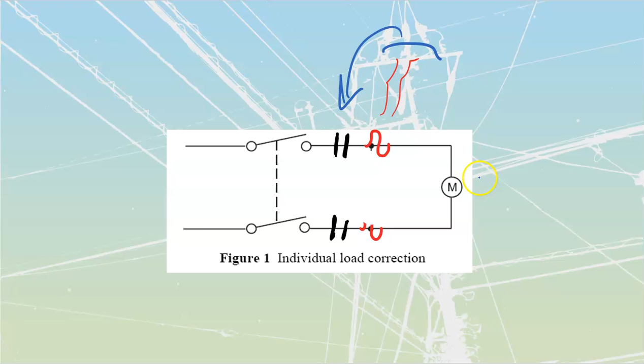What's it doing? Well, it's monitoring the current. Too much current goes through, creates too much heat, trips the switch, shuts the motor itself off. It just prevents us from burning out motors. This is sized based upon my motor's amps. There's going to be a whole thing inside of section 28 of your code book on how to size that. Now, as soon as I do power factor correction, what happens is I change my VA of that motor. Which means that if I size off of the VA of the motor, I'm going to have to reduce the size of my overloads.